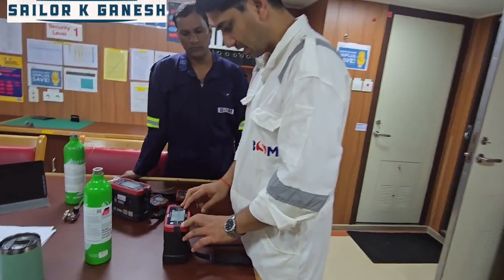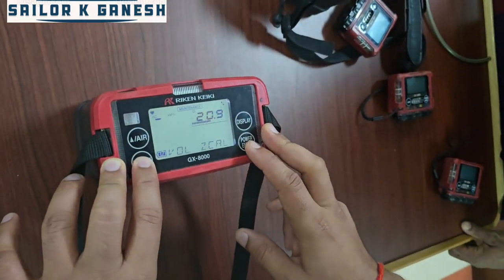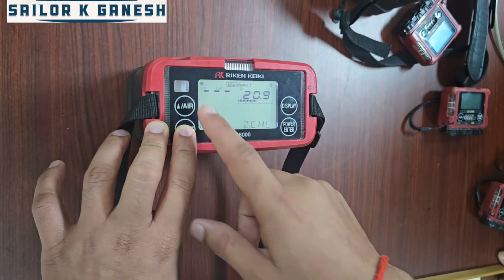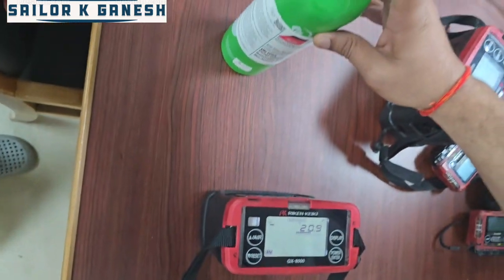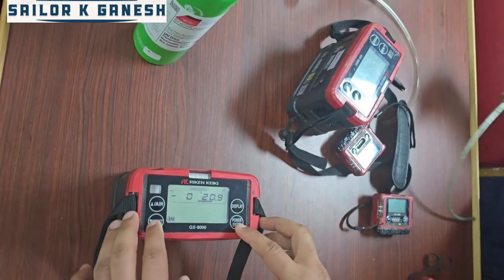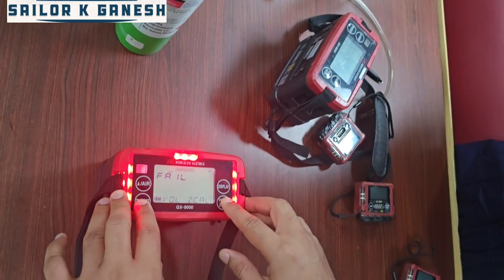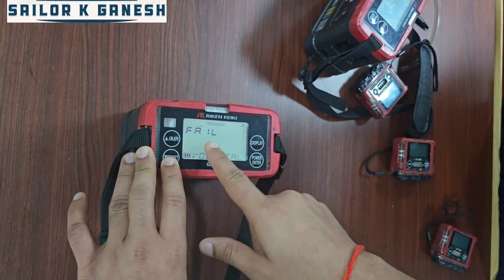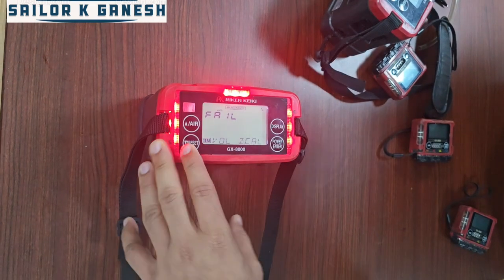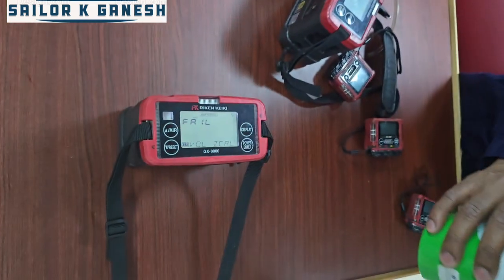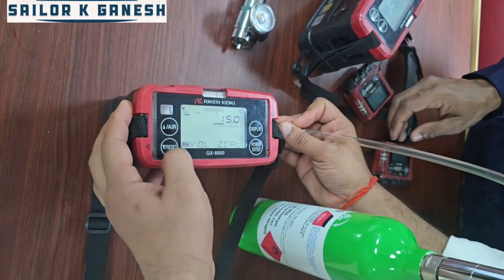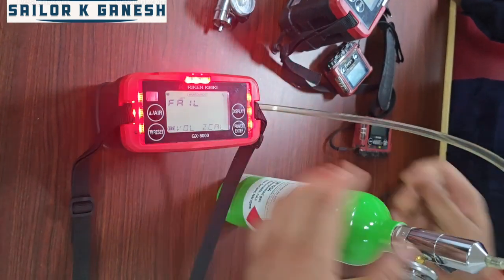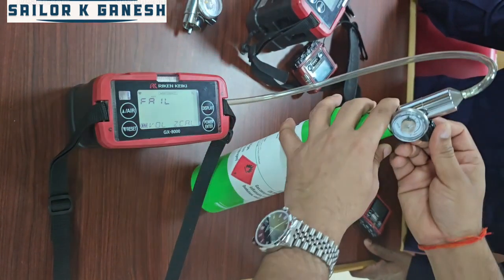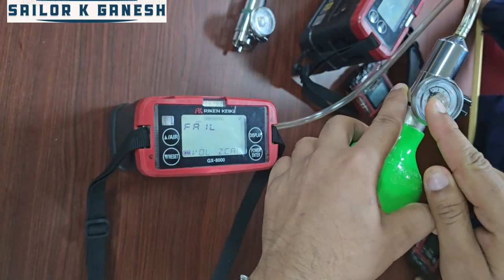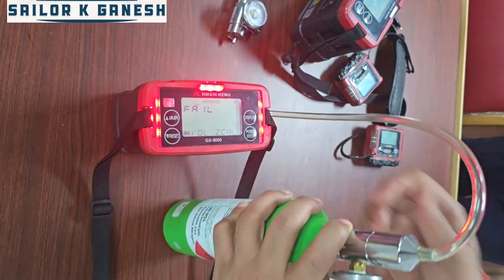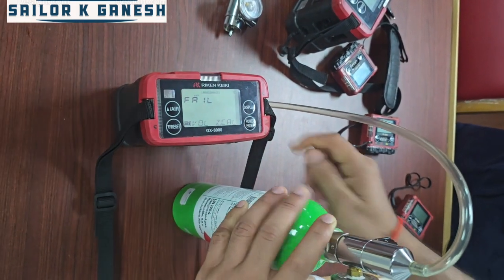So go to the zcal. One by one you can go for the volume calibration also for hydrocarbon. With the help of this gas meter you can calibrate for the volume also. So now you can see that volume calibration has failed because we have not connected the bottle. Volume zcal. The flow meter is not open fully. I think the bottle is empty. As you can see, the bottle is already empty. Never mind, we have another set of bottle.